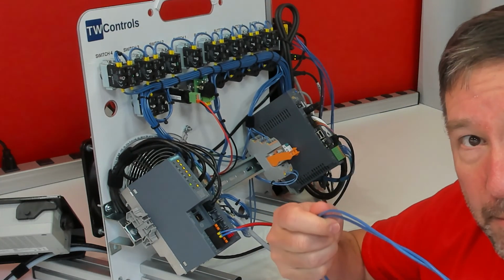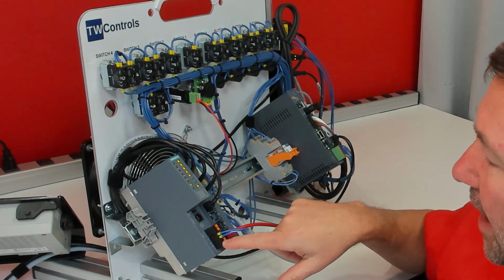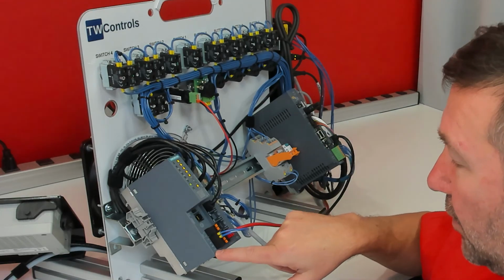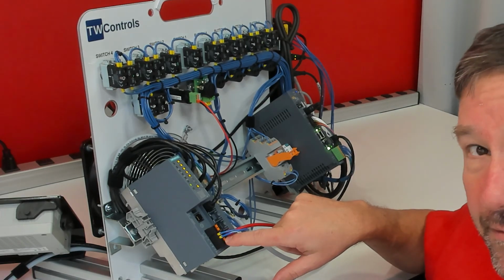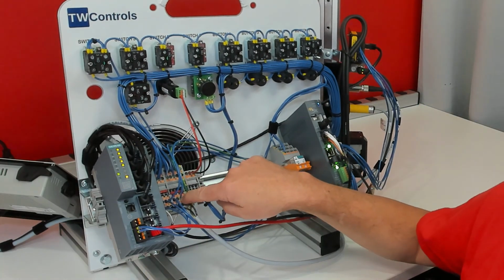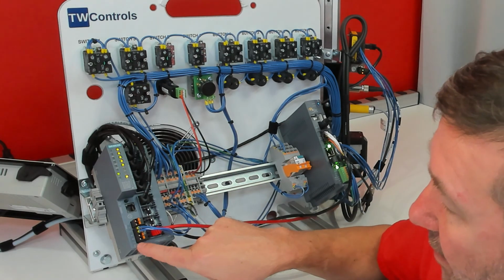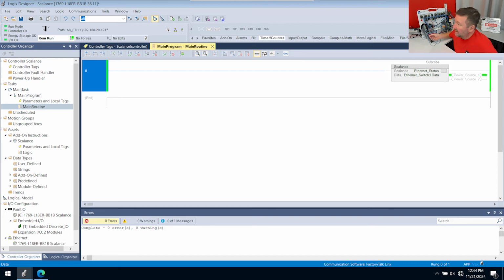So now let's grab a couple wires and let's hook up power source 2. The bottom one is the plus 24 volt for power source 2. The second from the bottom is the minus of it. So we're going to take a wire from the left set of terminal blocks to M2 and the other one to L2 plus. And when we touch the wire to the L2 plus, we get the power source 2 is good. And this typically would be a second redundant power supply. So one power supply goes out and that lets you know that it has.